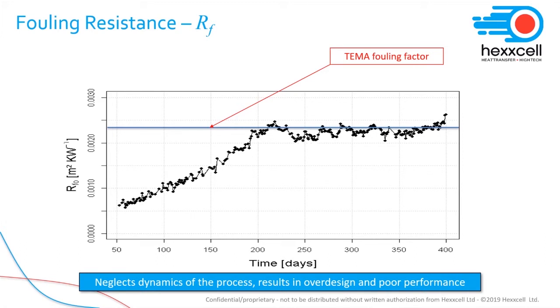This approach has been severely criticized in the past, since not only the origins of these fouling factors, particularly the thermal ones, are uncertain, but also because they were generated at the time, for example, when the average refinery run was much shorter than it is today. In fact, in the 40s, when the first TEMA edition came out, the average run was 3 months long, while today refineries tend to run for 4 to 5 years in between major turnarounds.